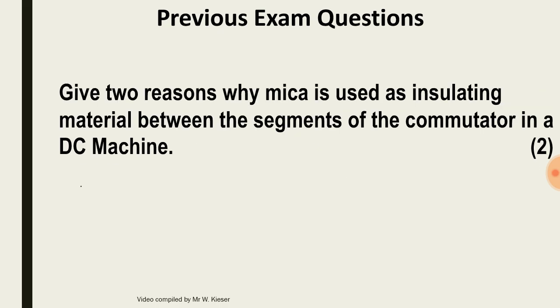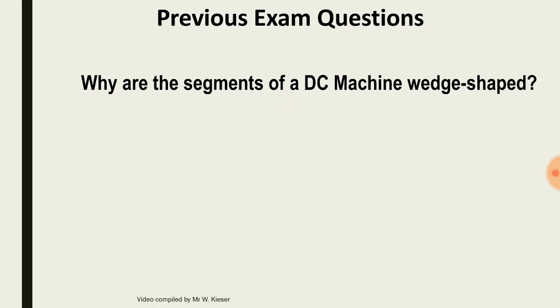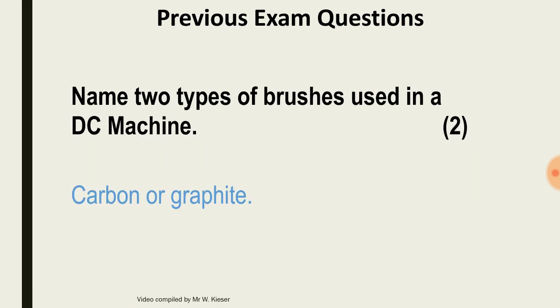Give two reasons why mica is used as an insulating material between the segments of the commutator: mica is a good insulating material and can withstand high temperatures. Why are the segments of a DC machine commutator wedge-shaped? The commutator segments are wedge-shaped so as to prevent them from moving out of position due to the centrifugal force of the armature. Name two types of brushes used in a DC machine: carbon and graphite.